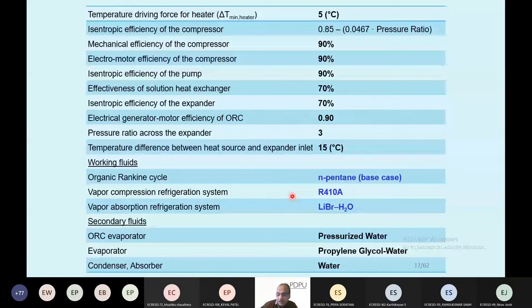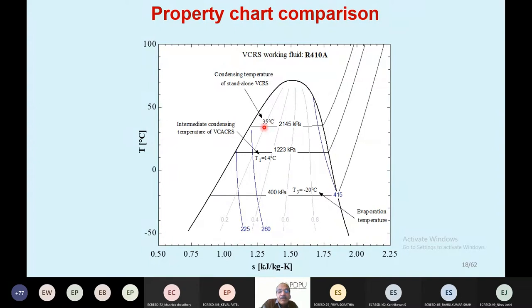Now that property chart, just for comparison purposes, if it is an absolute vapor compression system, then condenser temperature is 35 and it rejects the heat. Whereas in our case, when it is cascaded, almost at 14 or 15 degrees centigrade temperature, it rejects the heat to the evaporator of the vapor absorption system. That is the difference this particular diagram shows.